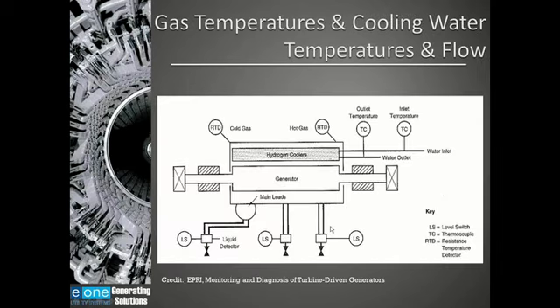Here's a simplistic view of what I just spoke about. Here you can see I have the inlet cooling water coming into my hydrogen cooler, and then I monitor the outlet. This will tell me how effectively I am removing heat from the generator. And then I have cold gas. Cold gas is always measured after the gas comes out of the cooler. That would be my cold gas. My hot gas is the hydrogen that's entering the cooler.